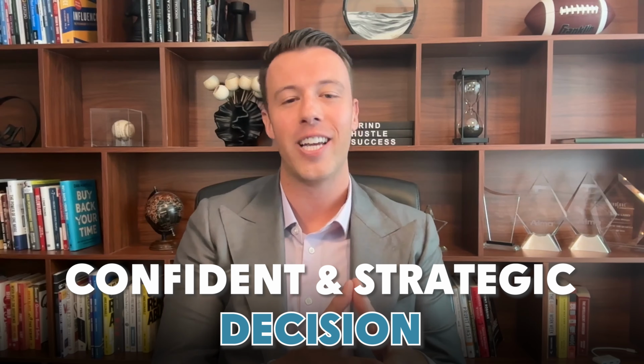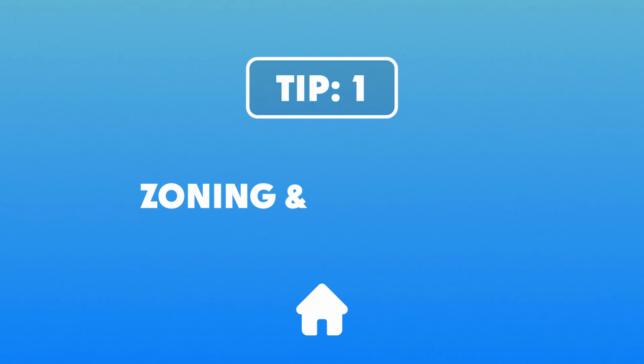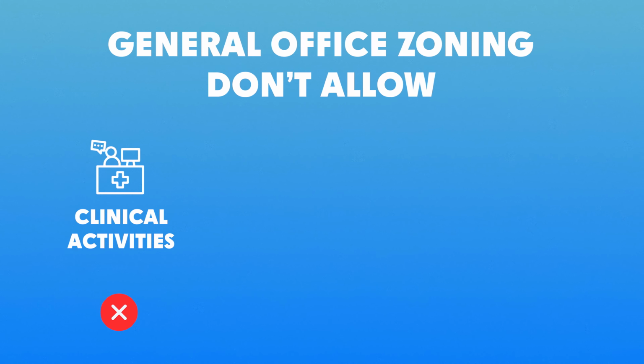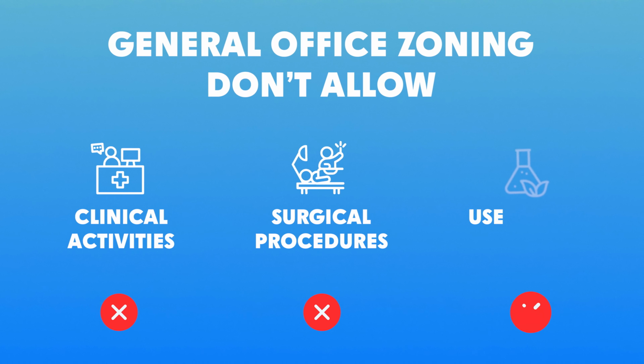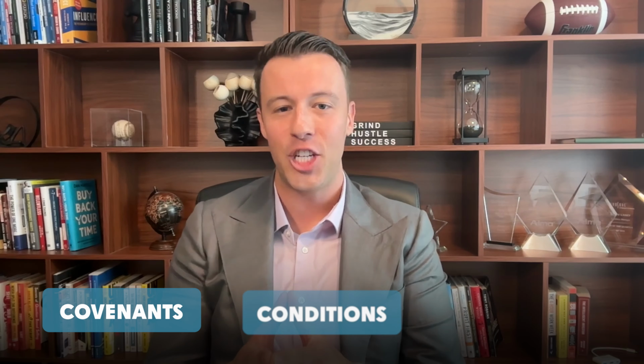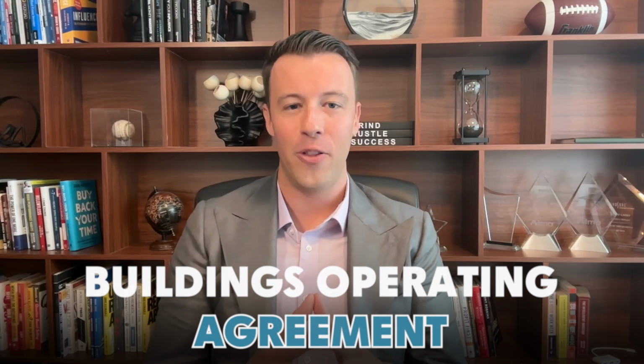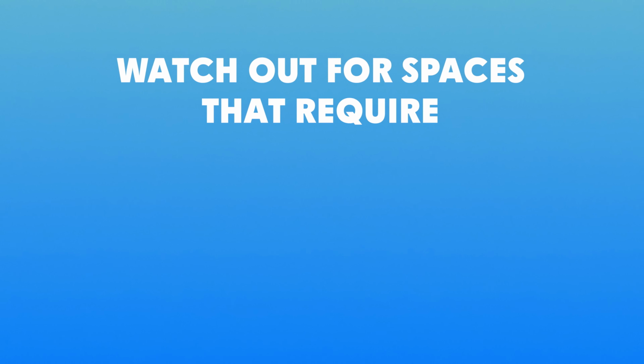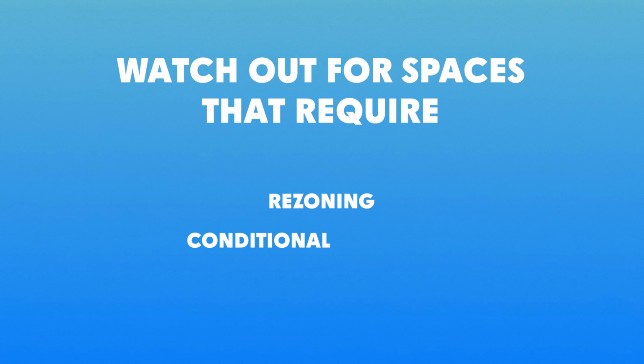Tip number 1, zoning and permitted use. Confirm that the property is zoned for medical use. General office zoning may not allow clinical activities, surgical procedures, or the use of biohazardous materials. Review any restrictions in the association bylaws, covenants, conditions, and restrictions, or the building's operating agreement. Verify use approvals directly with the city or the county. Watch out for spaces that require rezoning or conditional use permits, which can be very time-consuming and uncertain.